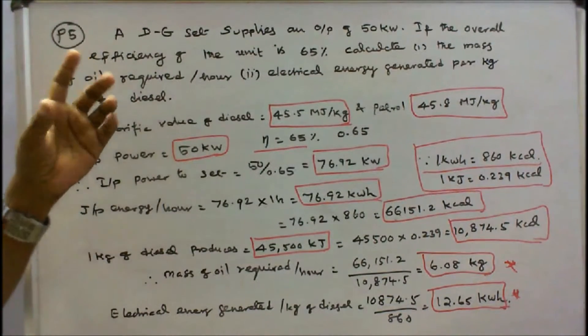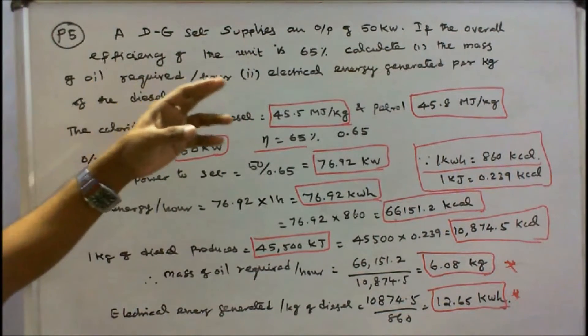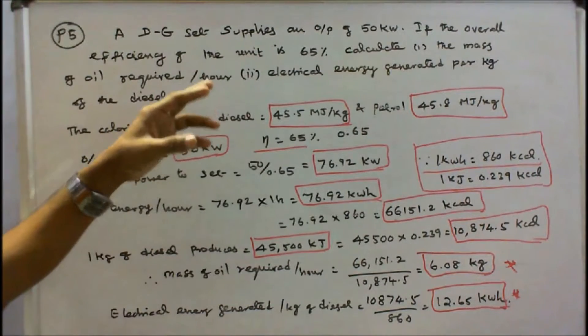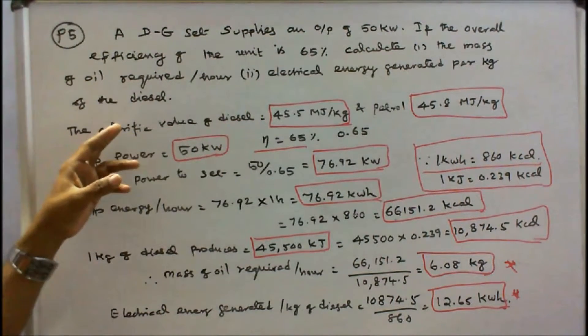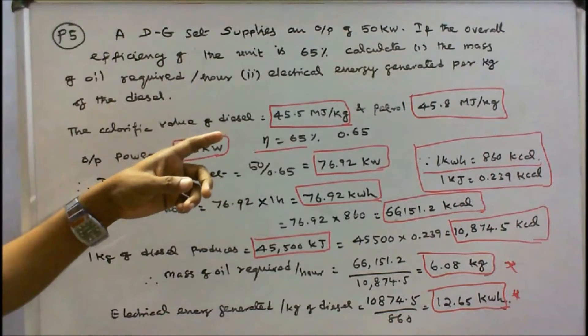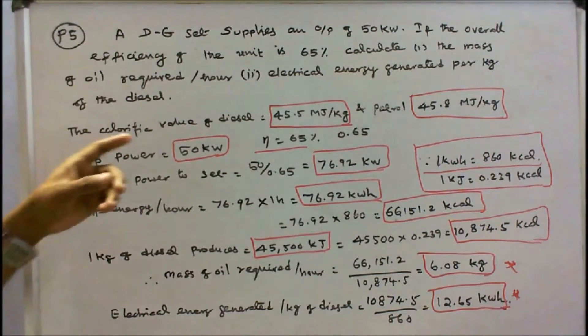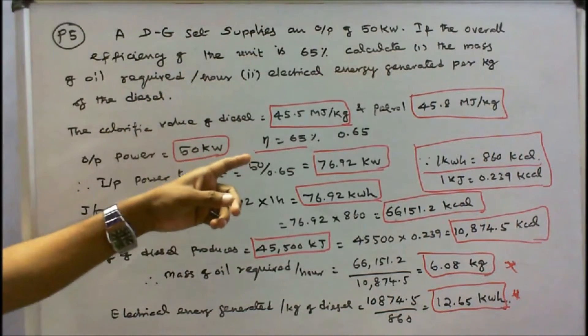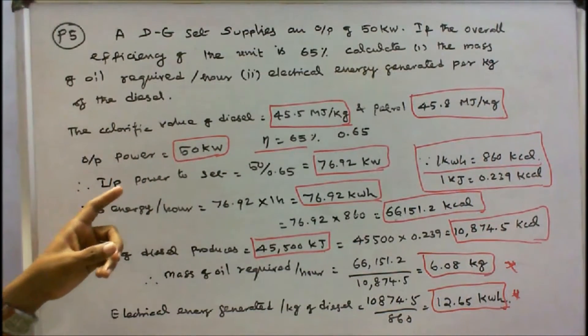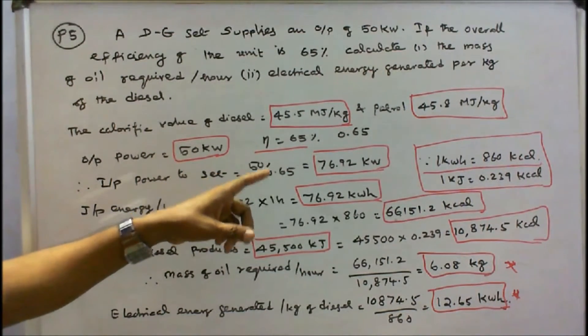Problem 5: A diesel generator set supplies an output of 50 kW. The overall efficiency of the unit is 65%. Calculate: 1) the mass of oil required per hour, and 2) electrical energy generated per kg of diesel. The calorific value of diesel is 45.5 megajoules per kg. Output power is 50 kW and efficiency is 0.65, so input equals 50 divided by 0.65, which is 76.92 kW.